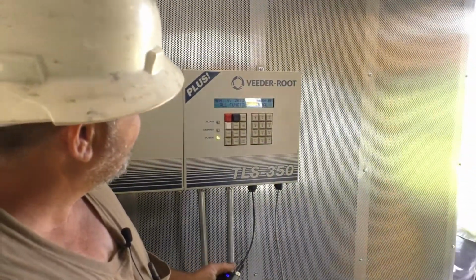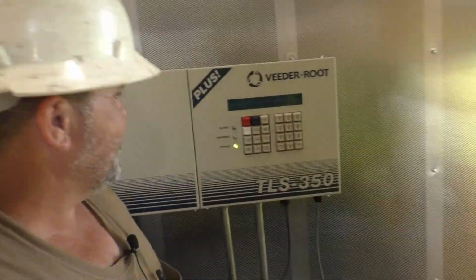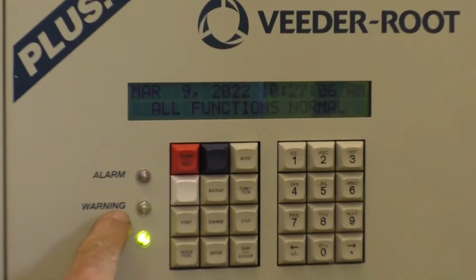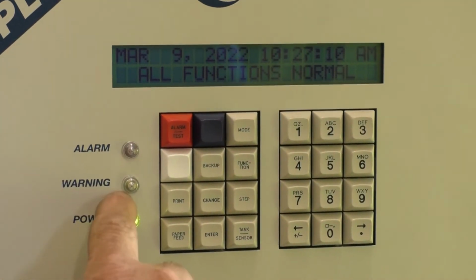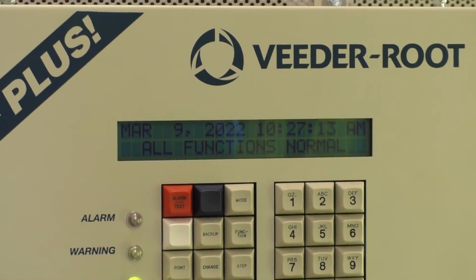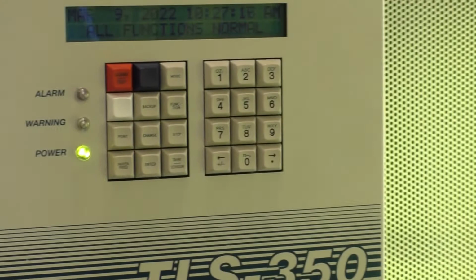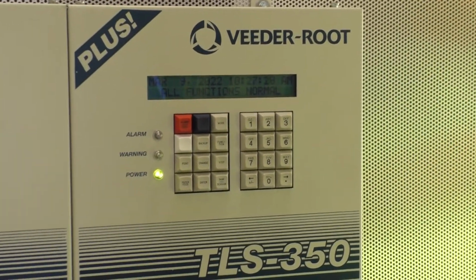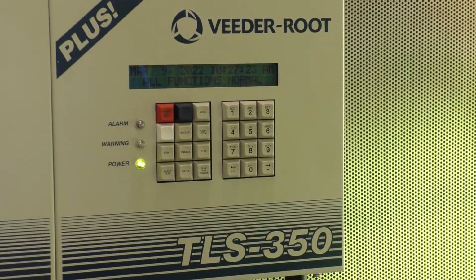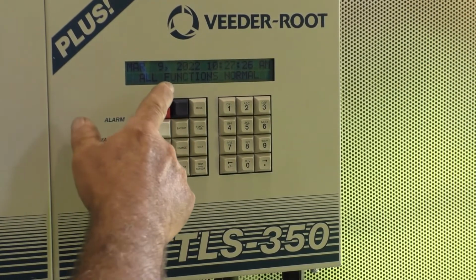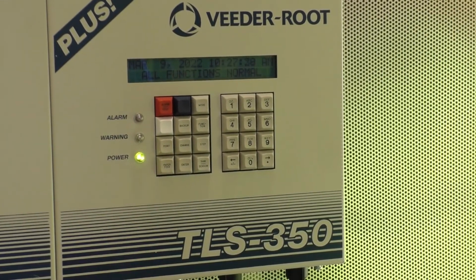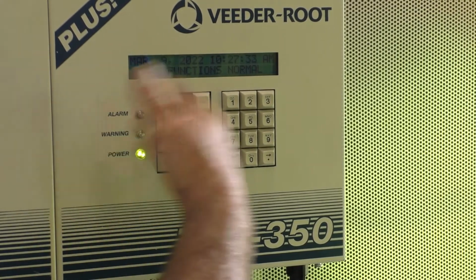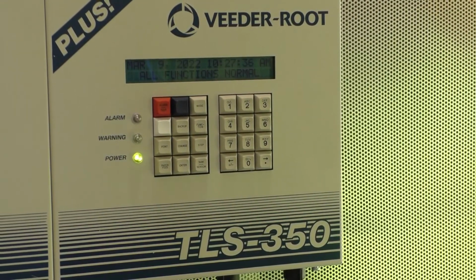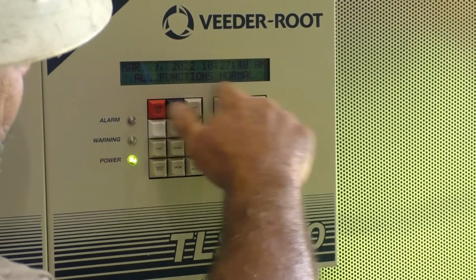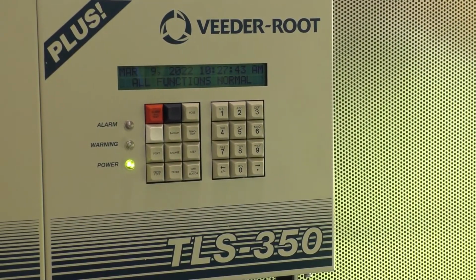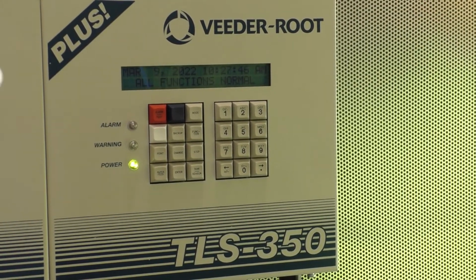All right, as you can see, when you walk up to it, you would hope that it says all functions normal. If there is an alarm, it'll either be a yellow light or a red light. A yellow light means it's a warning. Usually about the only time you're going to have that is if you've got low product or a low water warning in the tank or something like that. Other than that, most of your alarms are going to be red. To silence the alarm, just come up here and hit the red button. If it was just an intermittent alarm, it'll clear and go back to all functions normal. If the alarm condition is still present, it'll still flash red and it'll tell you what the alarm is up here. At that point, you'll probably call Billy or you'll probably call me to figure out what's going on and how to clear it.